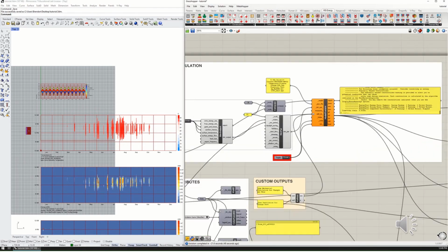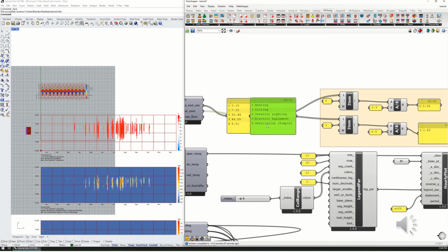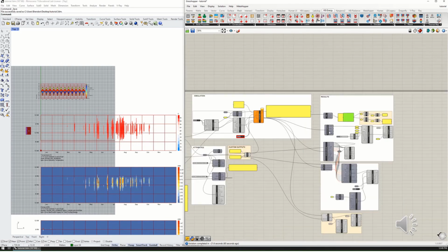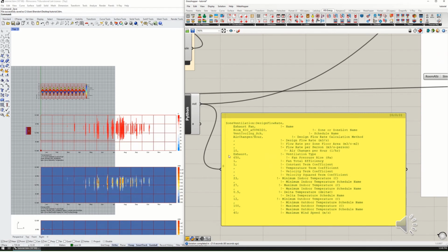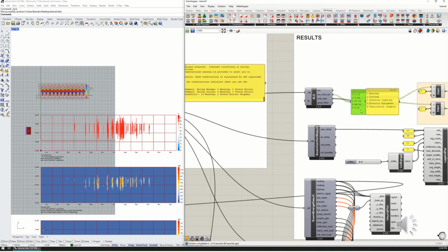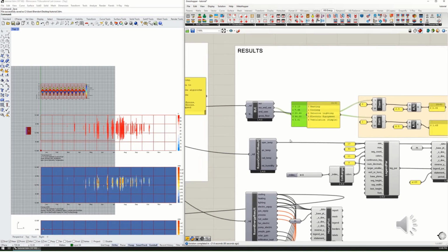Now, importantly, the fan energy does get reported here. So let me show you this. This is this 5.81 kilowatt hours per square meter. However, that number depends a lot on this number right here, the fan pressure rise, as well as some of these efficiencies and coefficients. And without knowing more about your specific building and the ventilation path, this is really difficult to estimate. So I wouldn't put too much weight on this number here. For now, I think we'll just ignore it in this class, and we can come back to it at a later point once we have specific designs.